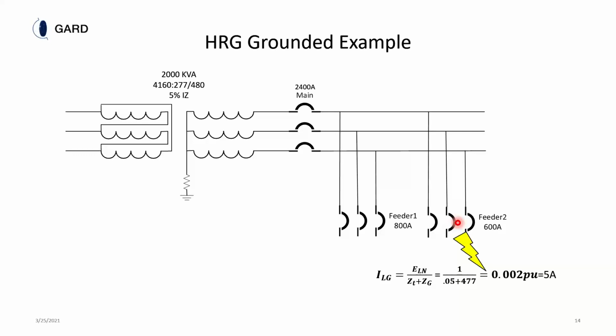And we have continuity of power, which is extremely important for data centers and many, many other industries, but we're going to predominantly talk about data centers now. What happens on the primary? We get an additional 0.3 amps of primary current for this 5 amp current on the secondary. So we have a ground fault on the system now, and we want to be able to find it without shutting anything down. So what we can do is, if we change the value of this resistor, we change the fault current.